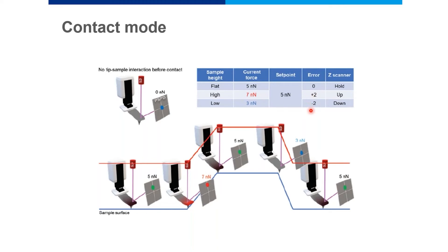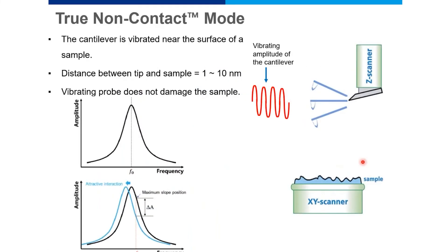The moment the signal is minus two, the feedback mechanism tells the Z-scanner to slightly move down so the set point of five nanonewtons is always maintained. The red line shown is the position of the Z-scanner moving up and down depending on the error signal. By driving the Z-scanner up or down to eliminate that error, an image in contact mode is generated at every point of the sample surface.